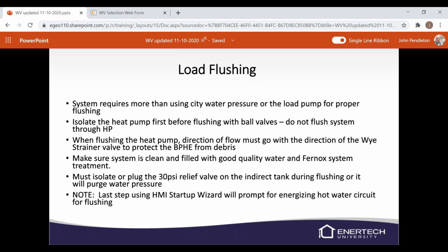Again, isolate or plug the relief on the water tank, or you will purge air or water out of it. And then the last step when you're doing your load flushing is to turn on the unit and go into the startup wizard. Basically it's going to energize the hot water circuit and shift that 3-way valve in there so you can flush the hot water circuit.